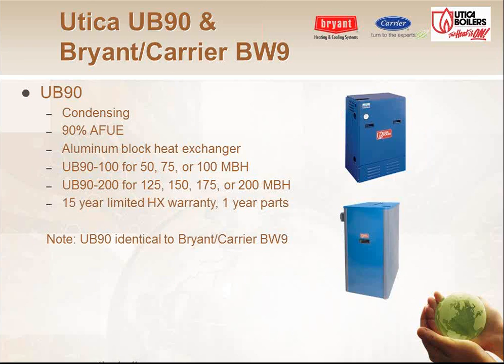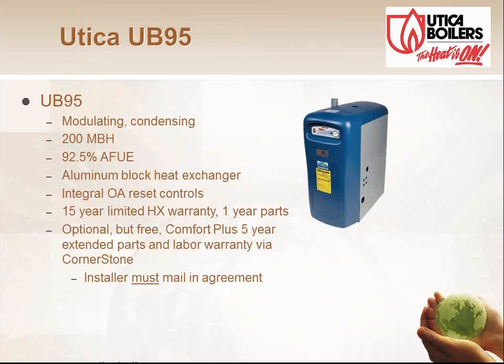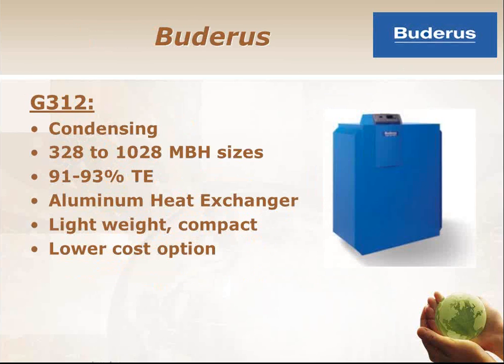One thing to keep in mind with some of these aluminum boilers, though, is that they can be very particular on what kind of glycol they can use. If you're just doing a commercial building or a house or something like that, no big deal. But if you're doing a snow melt system or something, you're going to add glycol, we tend to not recommend you use aluminum. We tend to stick with the steel boilers, stainless steel boilers in those cases.